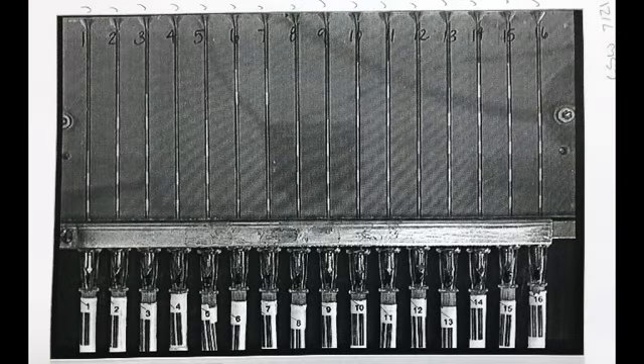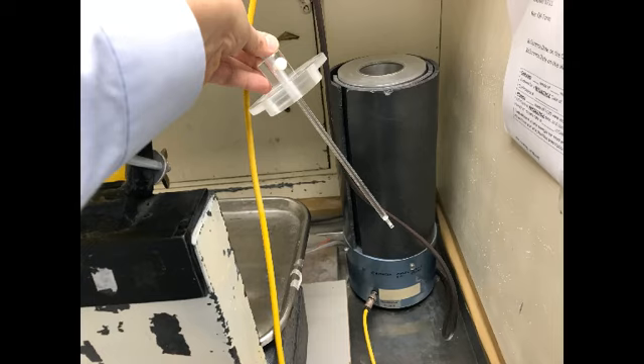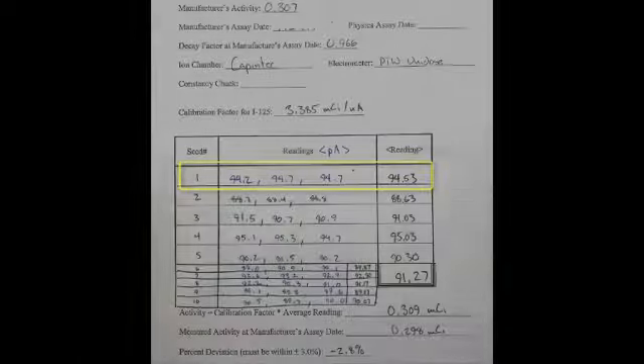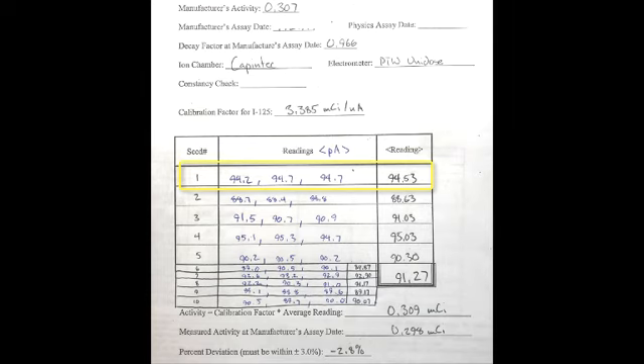The second important QA task is you need to verify the activity of the seeds that have been ordered. The manufacturer sends them with some activity specified, and the physicist needs to check that that is the actual activity. The rule is you should assay at least 10% of the seeds that are used in the implant, and those should be within 3% of the specification from the manufacturer. This is done in a well chamber. You put the seed in the well chamber, measure a current, and then from a calibration factor, where you know the number of millicuries per unit nanoamp, let's say, you can determine the activity of the seed.